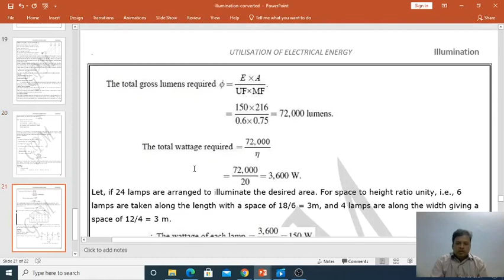The total gross lumens required is phi equal to E into A by UF into MF, that is 150 into 216 by 0.6 into 0.75, that is equal to 72,000 lumens. The total wattage required is 72,000 by eta, that is 72,000 by 20, equal to 3,600 watts. Let 24 lamps be used to illuminate the desired area, with space to height ratio unity, that is 6 lamps are taken along the length with a spacing of 18 by 6, that is 3 meters, and 4 lamps along the width, giving 12 by 4, that is 3 meters. The wattage of each lamp is 3600 by 24, that is equal to 150 watts.